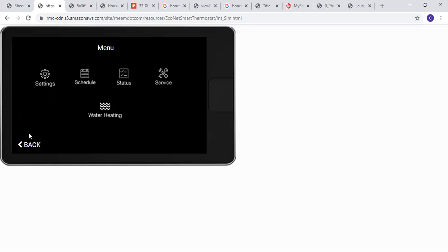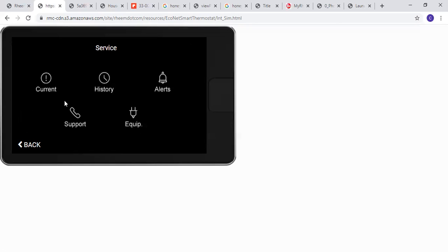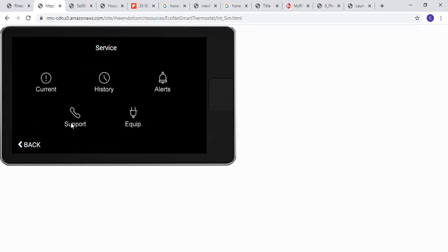Go into your settings here. If you would have an EcoNet water heater or pool heater hooked up, you can also control it from here. We'll go into service over here, so we know there's an error code there. Excuse me. It's telling us, so here it is, A004. It's telling us air source not detected. This furnace is not detecting the furnace or air handler.